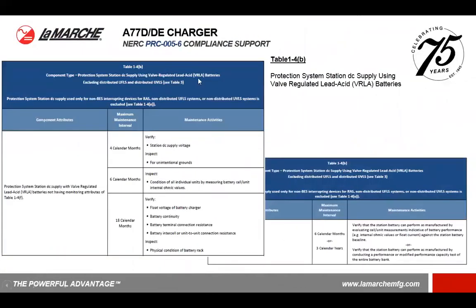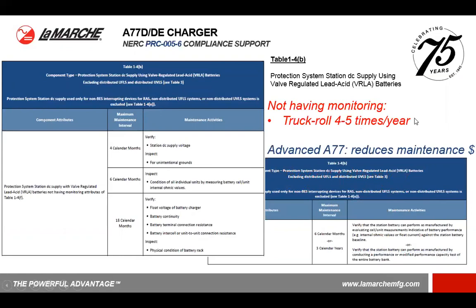A similar table, 1-4b, refers to valve-regulated lead-acid batteries. So very similar to the previous slide in that we're discussing battery systems not having monitoring attributes, but at 4 months, we have to do the same. We have to verify voltage and look for unintentional grounds. VRLA adds another step where every 6 months you have to perform an ohmic measurement on individual units. So for VRLA, you have even more truck rolls per year. Well, the A77 can reduce your maintenance cost.